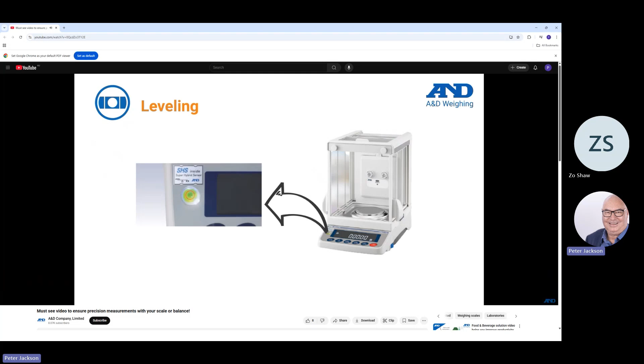We recommend that you check the calibration of the balance on a regular basis, using the following as a general guide. 1. When the balance is operated for the first time. 2. When the location of the balance is changed. 3. After performing any leveling adjustment. 4. After any changes in temperature, humidity, or air pressure. We understand that calibration is a critical component of precision and accuracy, and is why we offer external and internal calibration models to fit any application and budget needs.